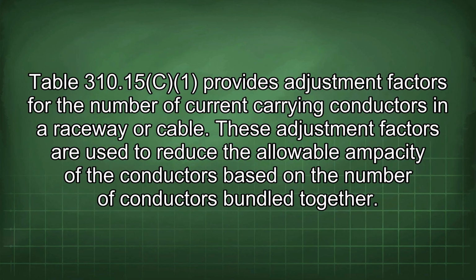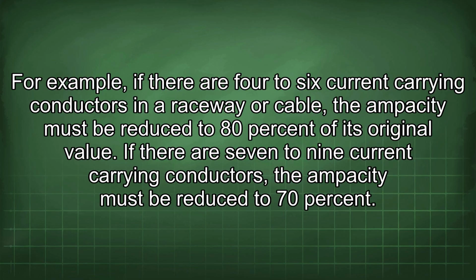Table 310.15 provides adjustment factors for the number of current-carrying conductors in a raceway or cable. These adjustment factors are used to reduce the allowable ampacity of the conductors based on the number of conductors bundled together. For example, if there are 4 to 6 current-carrying conductors in a raceway or cable, the ampacity must be reduced to 80% of its original value. If there are 7 to 9 current-carrying conductors, the ampacity must be reduced to 70%.